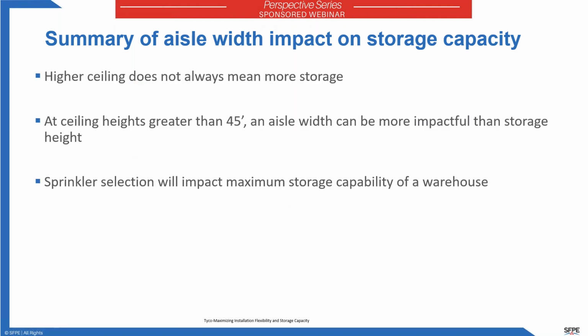So in summary, aisle width has an impact on storage capacity, and based on the aisle width, a higher ceiling height does not always mean potentially more storage. The aisle width can actually drive storage capacity more than the storage height or ceiling height. Ceiling heights that are greater than 45, as I said, have more impact than the storage height, and choosing a sprinkler will impact the storage capacity of the warehouse.